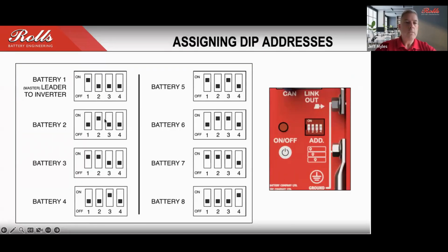to run it to the inverter. When you're assembling the stack, the primary battery will be the battery at the bottom of the stack. You need to assign, using the dip switches on the rear of each one of the batteries, the battery's position. Once the connections are made, you can refer to the dip switch table, which is included in the manual, and set up the four dip switch code for that particular battery. You're going to have from 1 up to 8, depending on how many you're stacking.